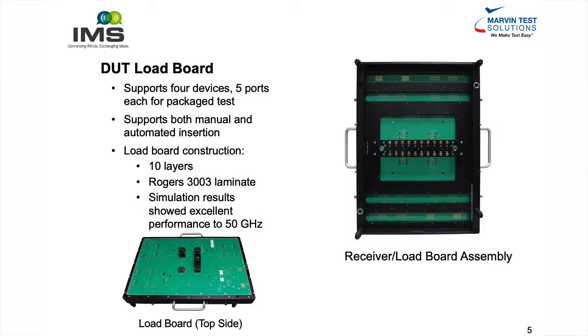Considerable time was spent designing the load board and simulating its performance. The load board construction consists of a 10-layer PCB using Rogers 3003 laminate with stitched signal and ground traces to guarantee uniform trace impedances. Simulation results showed excellent performance up to 50 GHz. The design supports 4 devices, each with 5 RF ports, 1 RF common, and 4 transmit-receive ports. Both manual insertion and automated insertion via an Epson NS8000 series handler are supported for production testing of packaged devices.